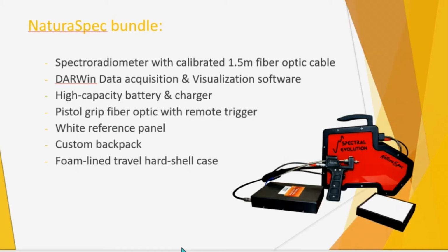It comes as well with a white reference plate. That white reference plate is like a spectral plate, 5 inches by 5 inches. It has a theoretically 100% reflectance. So what you would do when you take relative measurements in reflectance mode is that you first take a scan of that sample plate, which will be your reference, telling you that's where my signal is at 100%. And then you take your sample measurements, that are going to compare to that white reference.